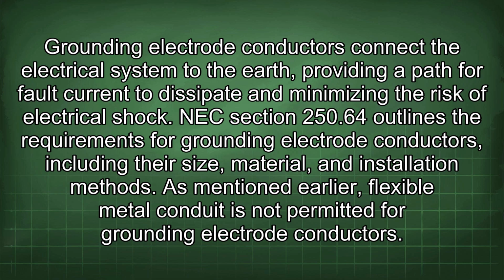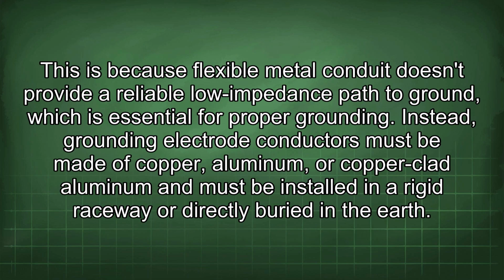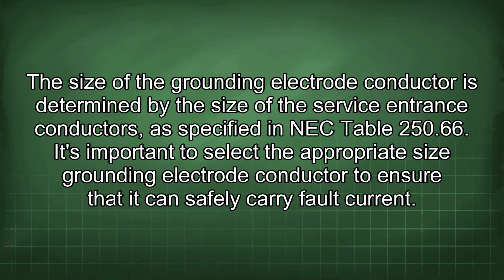As mentioned earlier, flexible metal conduit is not permitted for grounding electrode conductors. This is because flexible metal conduit doesn't provide a reliable low-impedance path to ground, which is essential for proper grounding. Instead, grounding electrode conductors must be made of copper, aluminum, or copper-clad aluminum and must be installed in a rigid raceway or directly buried in the earth. The size of the grounding electrode conductor is determined by the size of the service entrance conductors, as specified in NEC Table 250.66. It's important to select the appropriate size grounding electrode conductor to ensure that it can safely carry fault current.